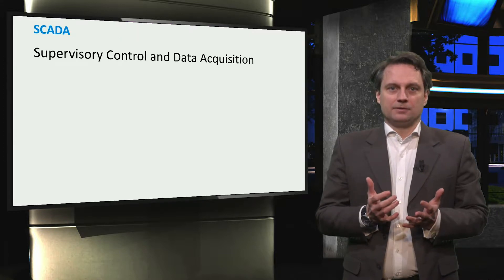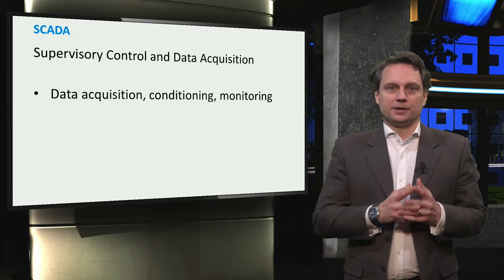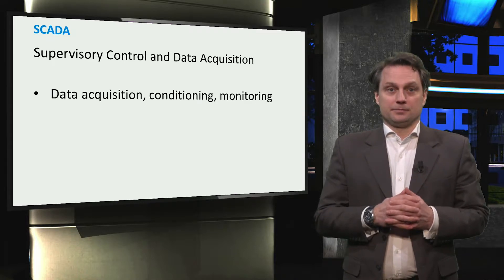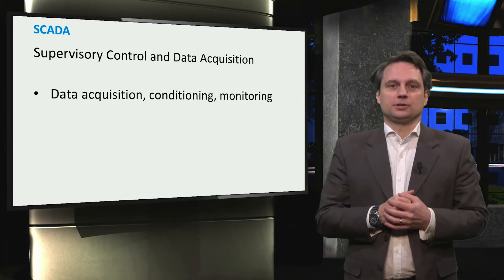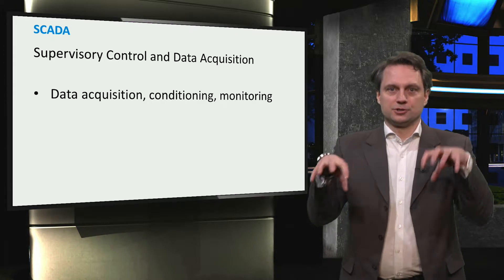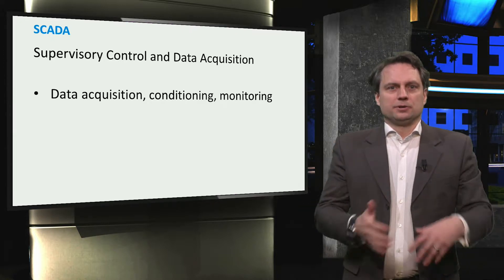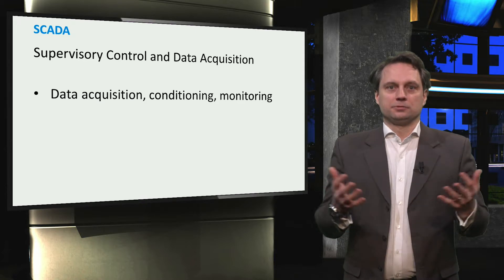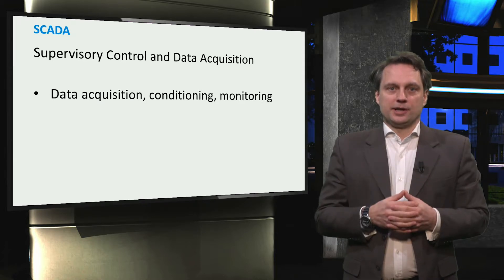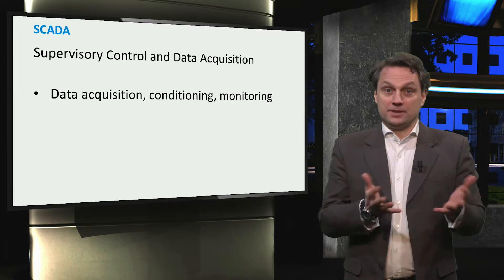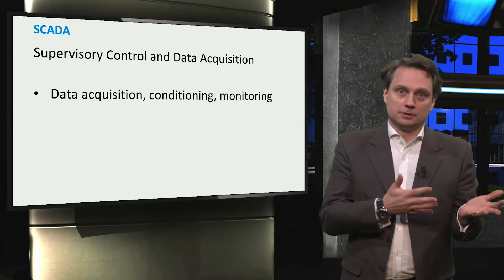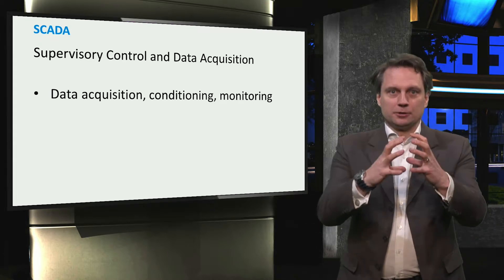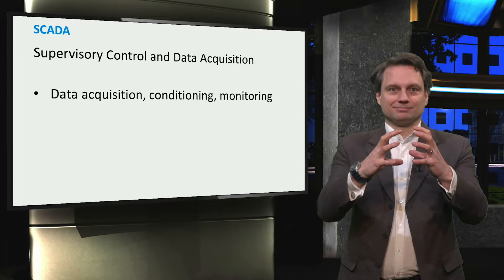SCADA stands for Supervisory Control and Data Acquisition. Data is first collected at remote substations. These substations serve as hubs in the energy system, and they contain transformers, switching equipment, protection relays, and a variety of sensors to monitor those devices. The data is then delivered via cable or radio communication systems to a central location called the control center.